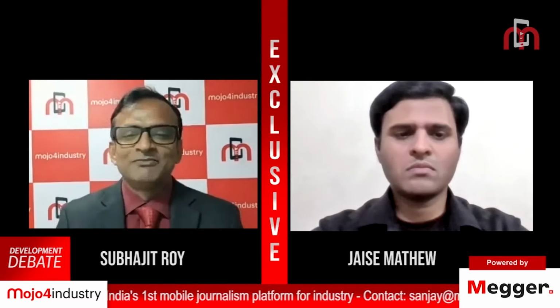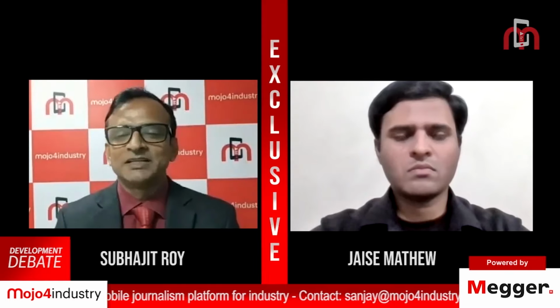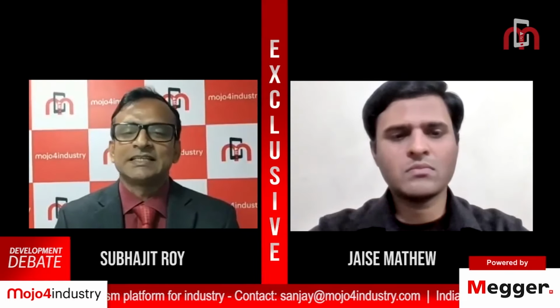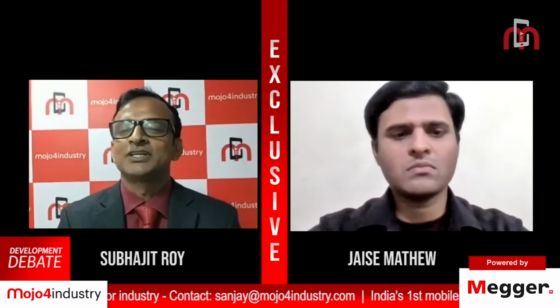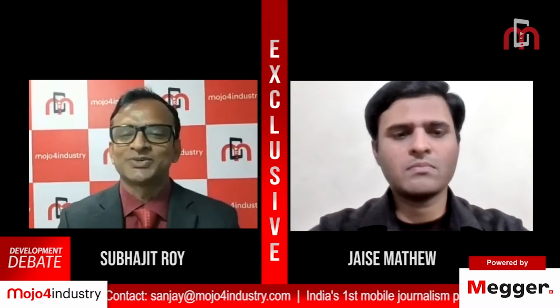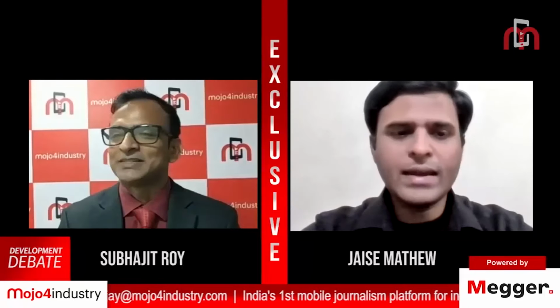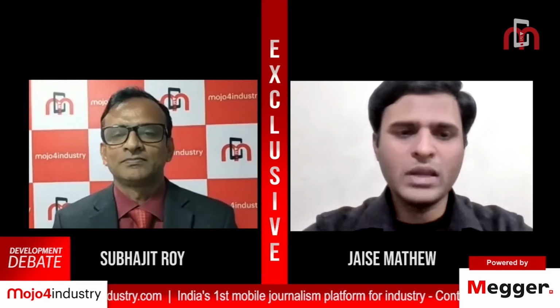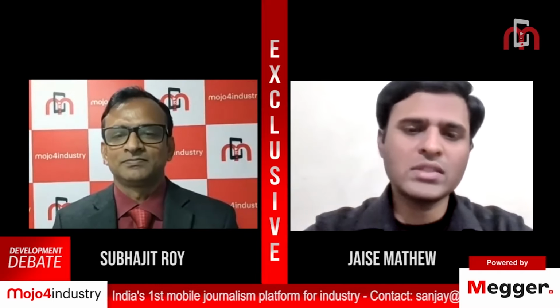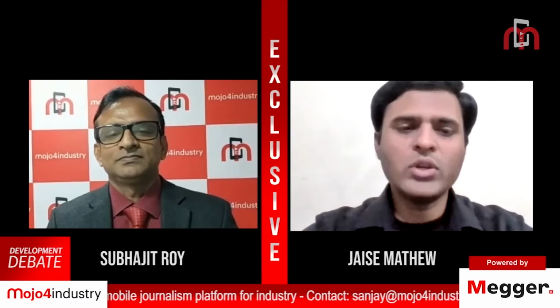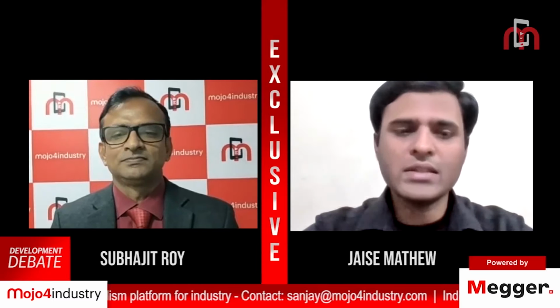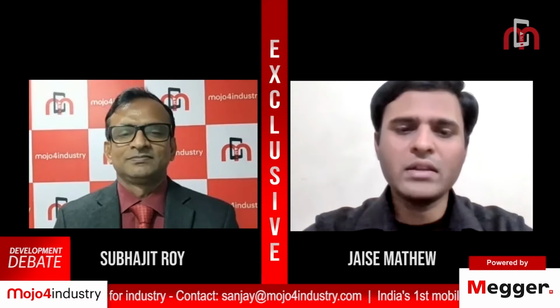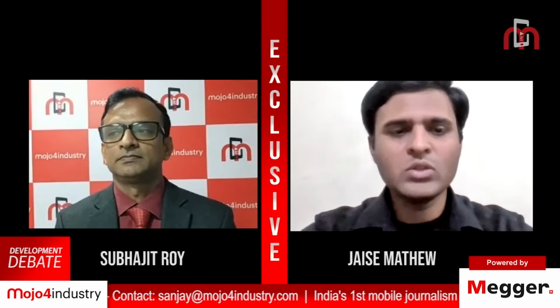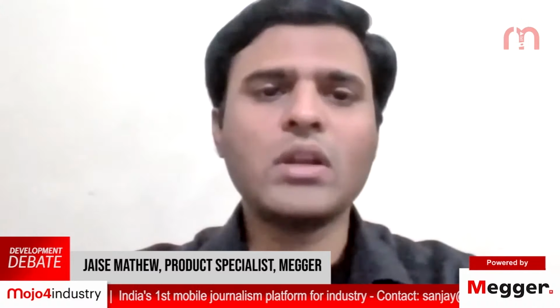So, Mr. Mathew, before you start with your presentation, can you explain why maintenance of electrical assets is critical, especially for medium voltage ones? I think that will help us to set the tone of the session. As per the standards which we follow, mainly IEEE states in the 3006 standard, in the table, that 32% of the failures in the electrical assets are due to the inadequate maintenance work which is done on the electrical assets. So they have categorized the different types of electrical assets and the percentage of failures on the electrical assets because of the inadequate maintenance work.